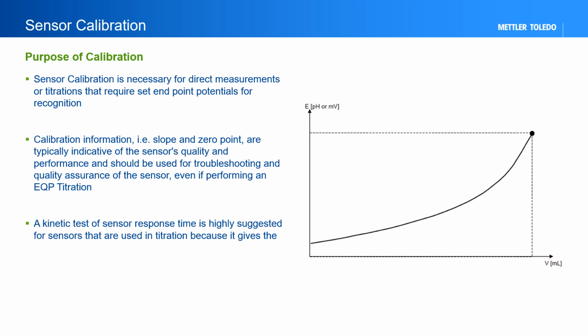An equivalence point titration, which utilizes an inflection point determination based off the first or second derivative of the generated titration curve, does not require a sensor calibration. Calibration-yielded data, such as slope and zero point, are indicative of the sensor's ability to provide accurate measurements. So, even if a calibration is not required, calibration methods should be in place for troubleshooting and performing quality checks of your sensor.